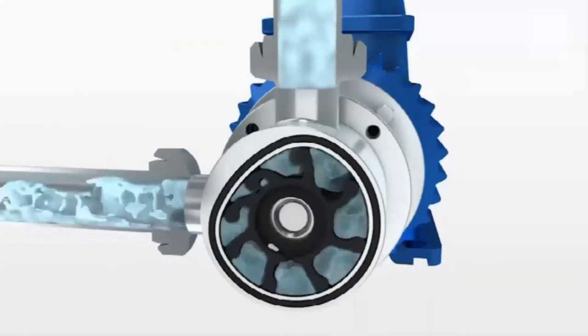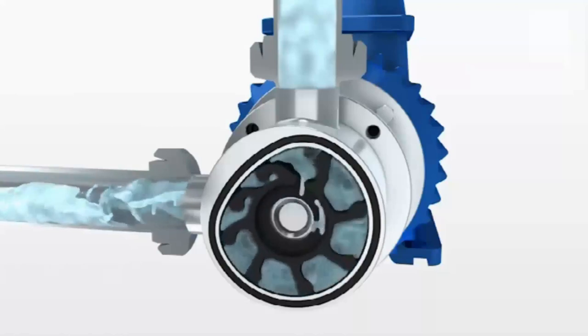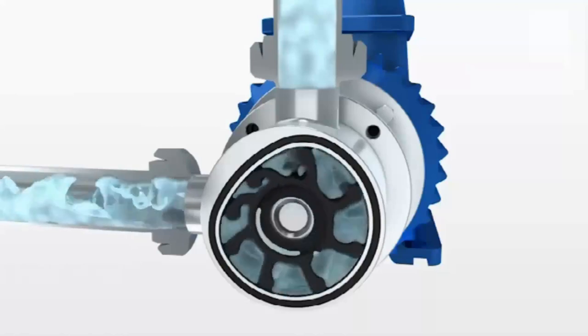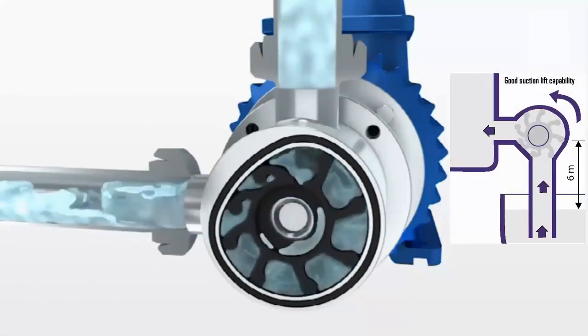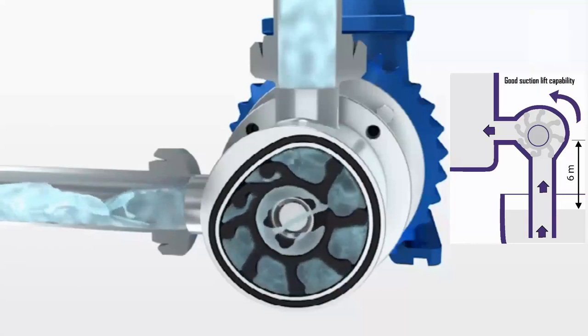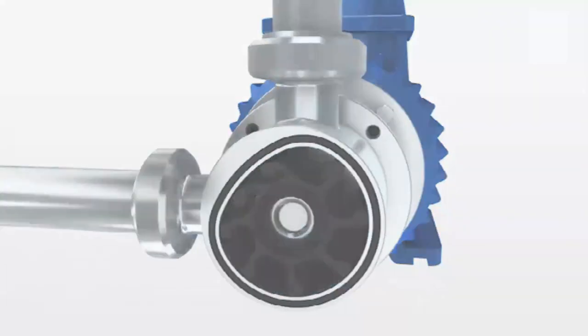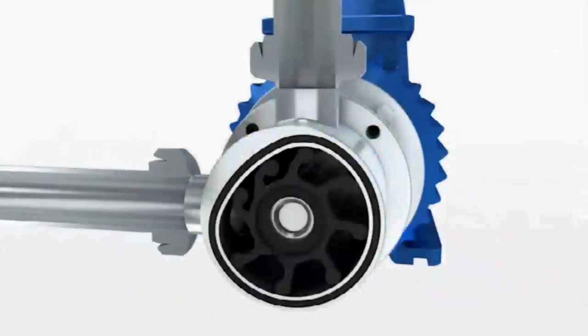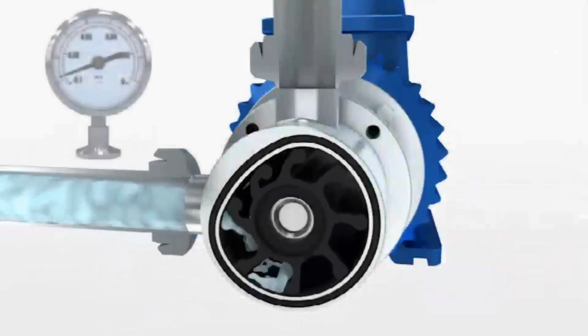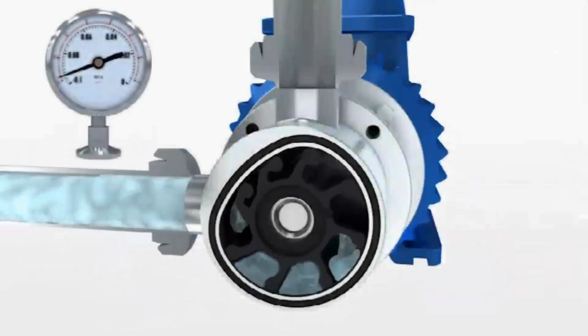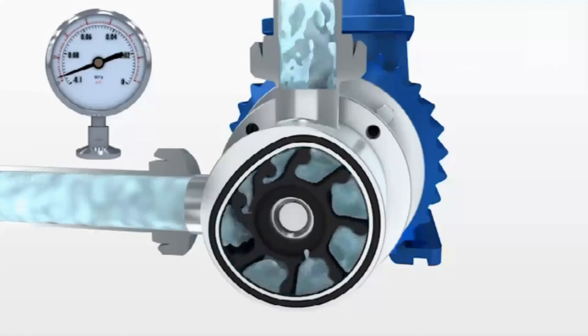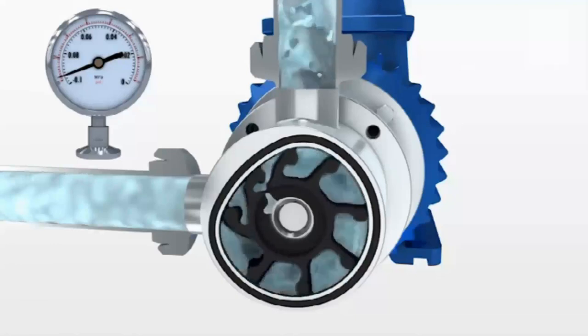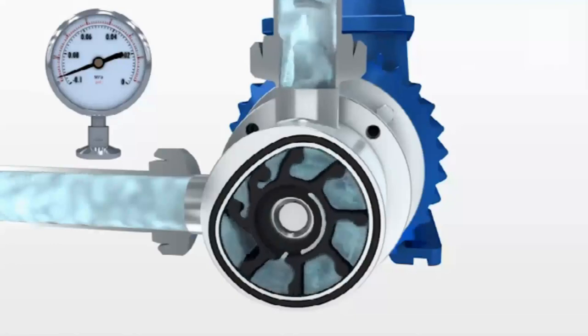A special characteristic of the flexible impeller pump is that it is able to maintain a tight seal between the impeller and the pump casing, giving it good suction lift capability. The gentle pumping mechanism means that shear-sensitive fluids can be handled without damage to their structure — for example, food products such as olives that can be squashed, or cream that can become thicker when agitated.